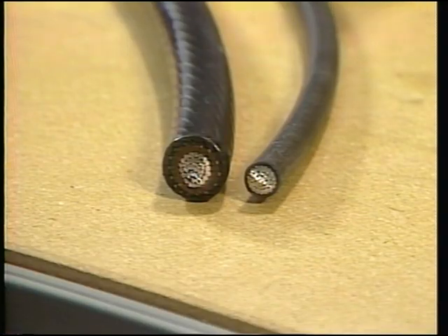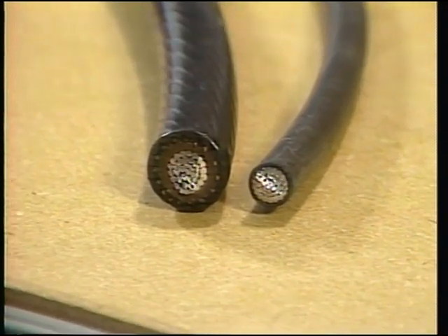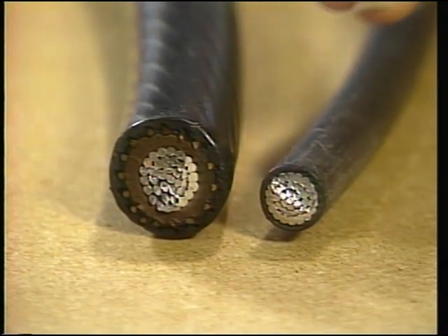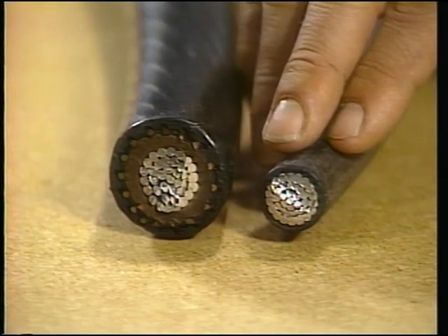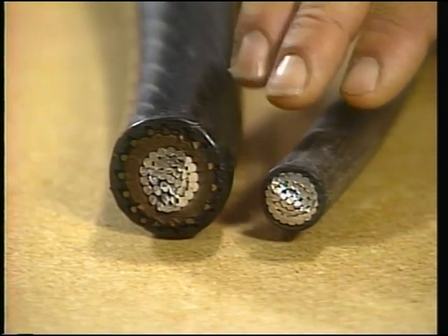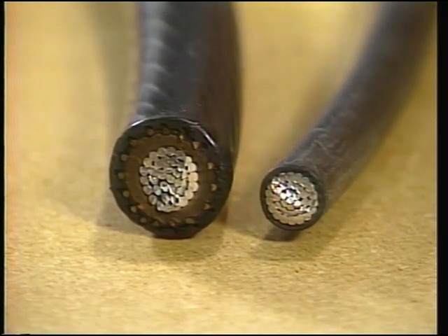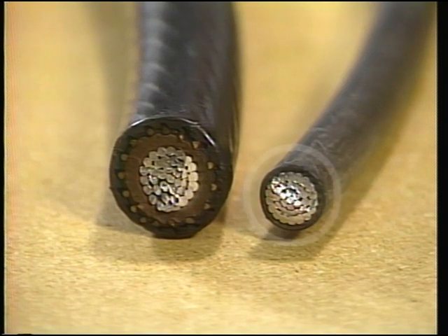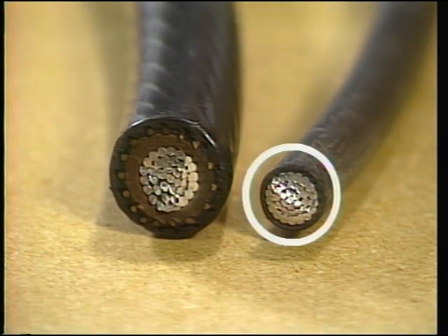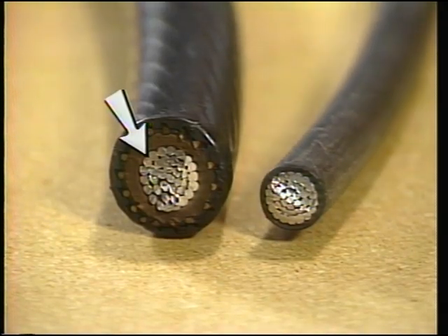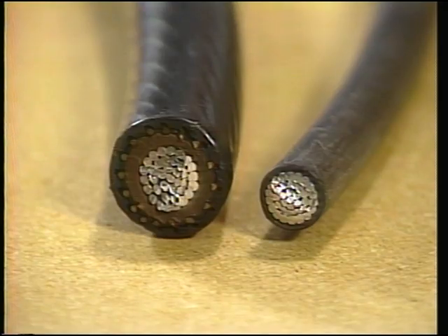Now, before we get to those splices, however, let's talk a little about how secondary and primary cables differ. You can see right away that the secondary cable has fewer layers than the primary cable we've seen. The cable is designed with fewer layers because secondary voltages don't demand as much from the cable construction. For instance, because of the lower voltages, there isn't as much voltage stress on the insulation layer. This reduced stress means there's no need for the conductor semiconductive shield. The reduced voltage stress also means there's no need for the semiconductive insulation shield layer.